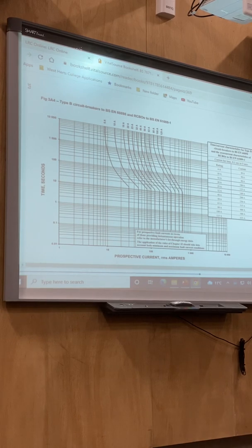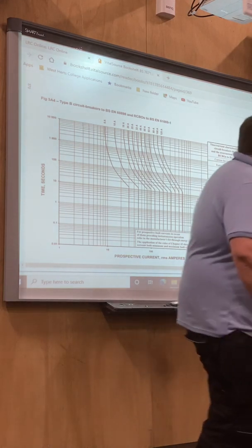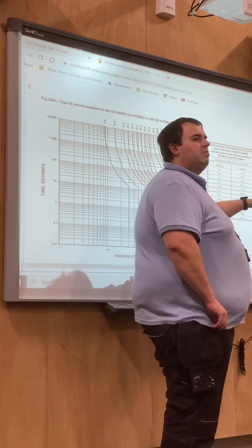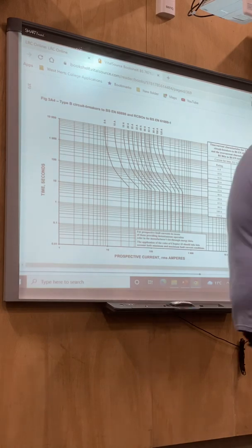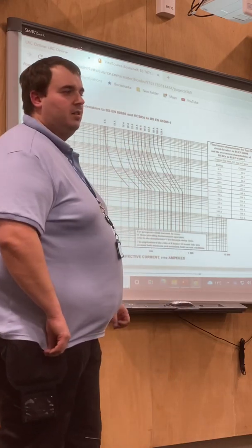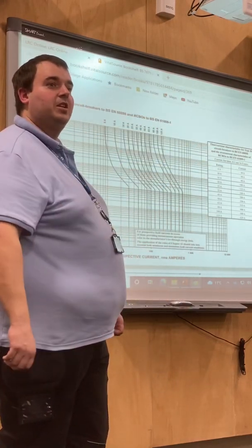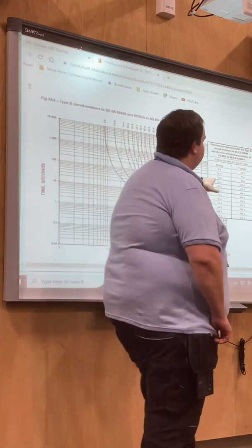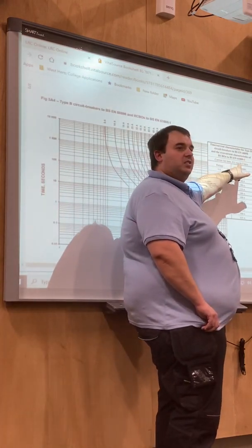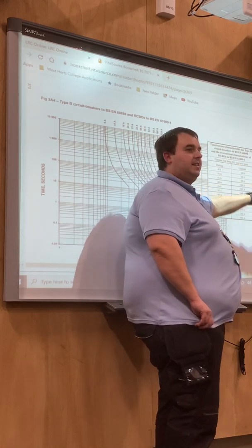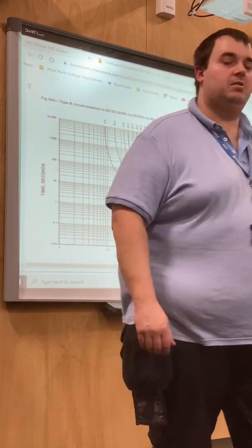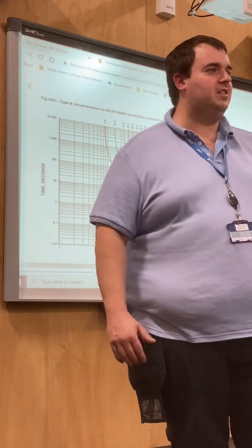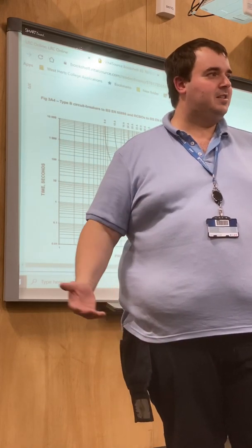So the first protocol I'd always recommend is to look at this little piece here. It should be page 370. Have you found it? B type RCDs and MCBs. Yes, 16 amps. So a 16 amp breaker to achieve a 0.1 second disconnection time only needs 80 amps. Is our fault current above 80 amps? 164 amps is above 80 amps, isn't it?